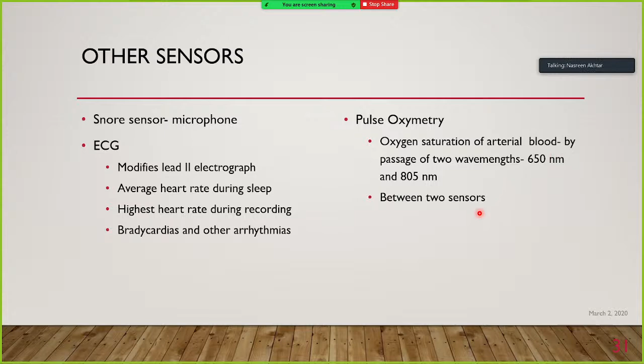Pulse oximetry, which is the most important component of polysomnography to diagnose obstructive sleep apnea, what is the principle? It assesses the oxygen saturation of arterial blood by passage of two wavelengths. There is a spelling error here, sorry. 650 nanometers and 805 nanometers. So whatever is the saturation of hemoglobin, that is HbO2, based upon that, between the two sensors, the light is going to pass, and it will detect by calibration basically the oxygen saturation of the arterial blood.